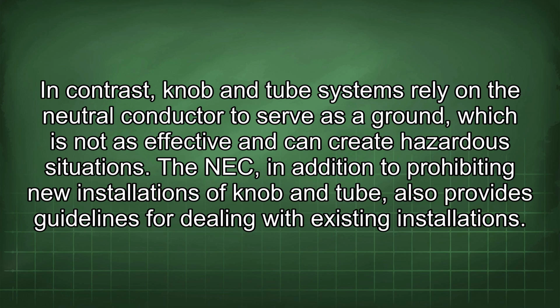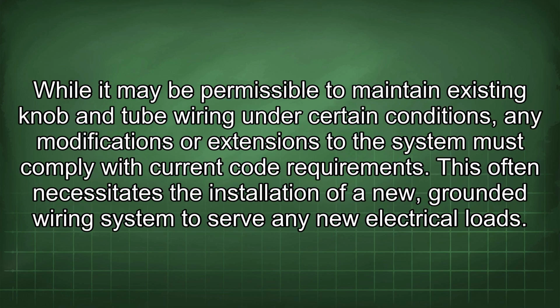The NEC, in addition to prohibiting new installations of knob and tube, also provides guidelines for dealing with existing installations. While it may be permissible to maintain existing knob and tube wiring under certain conditions, any modifications or extensions to the system must comply with current code requirements. This often necessitates the installation of a new, grounded wiring system to serve any new electrical loads.